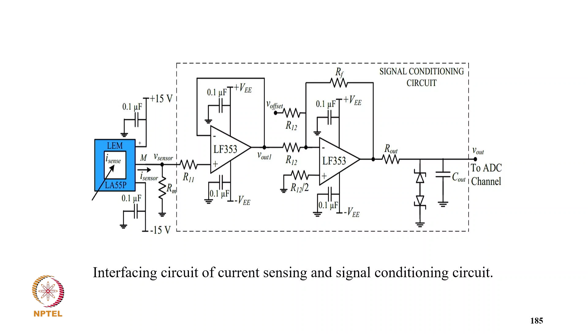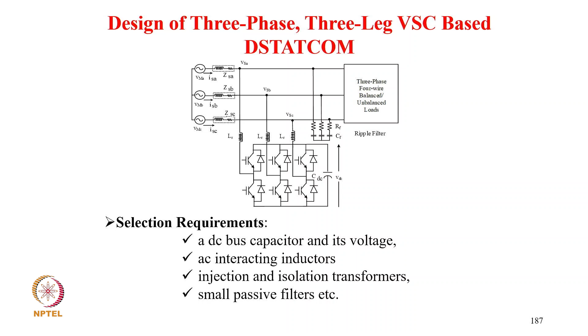So coming to the designing of D-STATCOM, taking the case of a 3-phase 3-leg voltage source converter for D-STATCOM. The selection requirements are a DC bus capacitor and its voltage, an AC interfacing inductor, an injection and isolation transformer, a small passive filter, etc. Now coming to the design parameters of D-STATCOM. The D-STATCOM is designed for compensating a reactive power of 50 kVA with a safety factor of 1.1 in a 415 volt 50 Hz 3-phase distribution system. So the D-STATCOM rating is SDST equal to 50 kVA, and the AC line frequency is 50 Hz. VSP is VLL by root 3, that is 239.6 volt. The safety factor is 1.1. So I D-STATCOM is 1.1 times SDST upon root 3 VLL, and putting in the values it comes to 76.516 ampere.